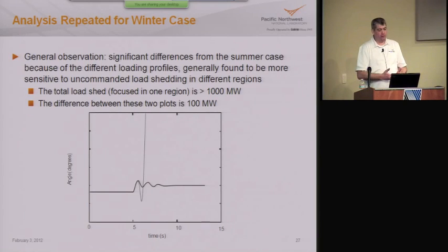And that was found when we looked at the winter case. The winter case is more lightly loaded. There's less power assumed in our base case. And we found a case where we can make this grid go unstable with between 1,000 and 1,500 megawatts, so less than the summer case. And this is a different location, because the sensitivities are different for the different loading profile. The difference between these two plots is 100 megawatts. So we progressively increased the amount of load shed, and in this one region, between 1,000 and 1,500 megawatts, we found that was enough load shed to create an instability and break up the system into islands.